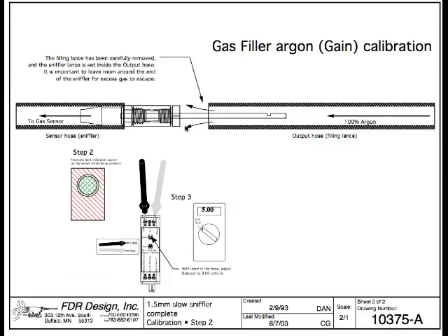Step two is going to be telling the machine what 100% argon looks like. So for that to happen, we're going to have to put the sniffer lance, the vacuum lance, inside the output hose, inside the argon output hose. So now the machine is going to be sucking 100% argon. In order to keep the machine running, we're either going to have to flip the sensor override switch up, or you're going to have to press and hold the start button. Either one will keep the machine running. Otherwise it'll beep and shut off at the end of the cycle.